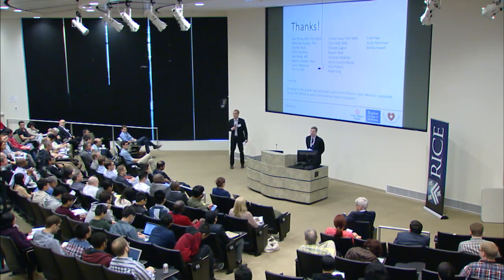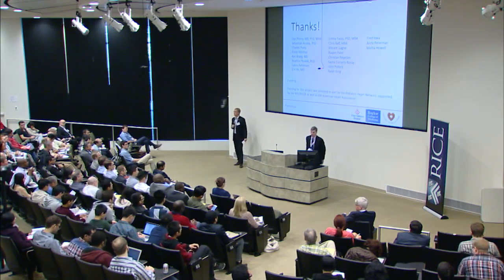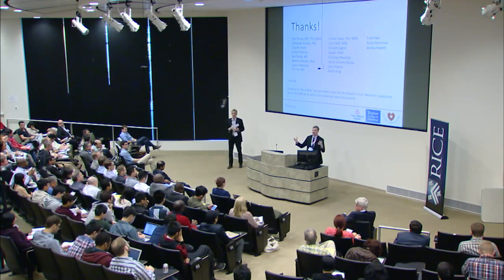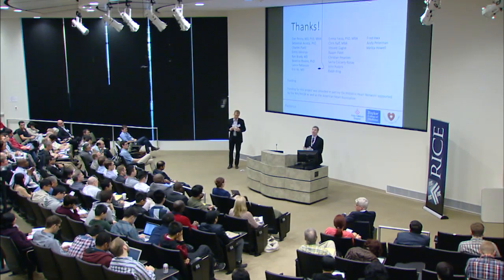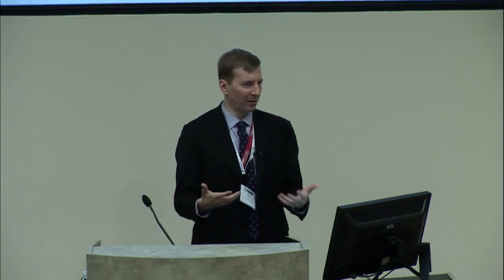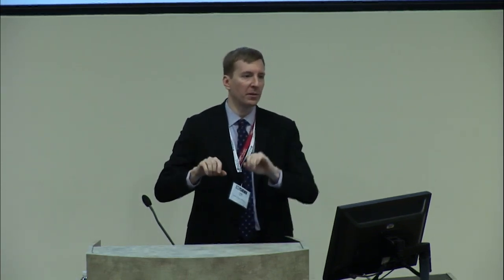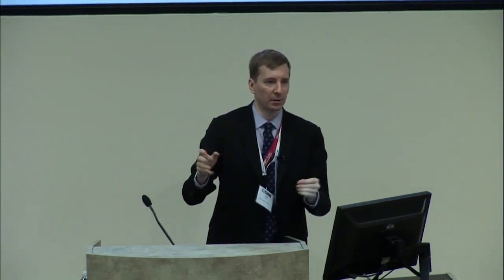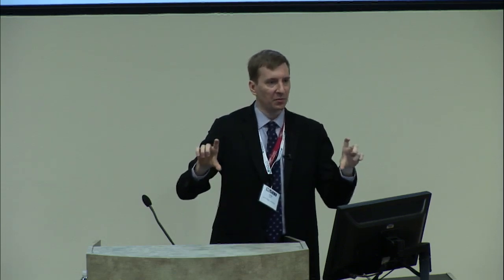And there's kind of two answers to that. The platform itself is designed to simply provide the algorithm with all the data that's available, right? Because what's noise to one algorithm may actually be signal to another. And to have the platform make that decision is not really correct, right? It should be up to the developer of the algorithm to do all of the filtering and all of the signal processing in order to make that determination. So what the platform provides is a normalization layer. So as a developer, you don't have to worry about whether you're getting data from a GE monitor, or a Philips monitor, or a Draeger, or whatever, right? You have a consistent view onto the data.